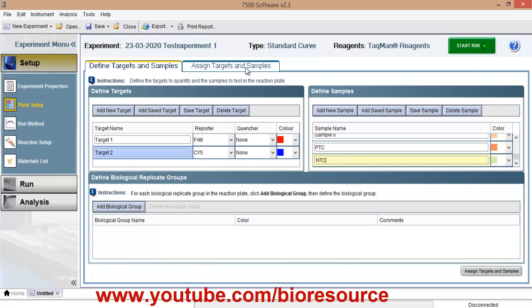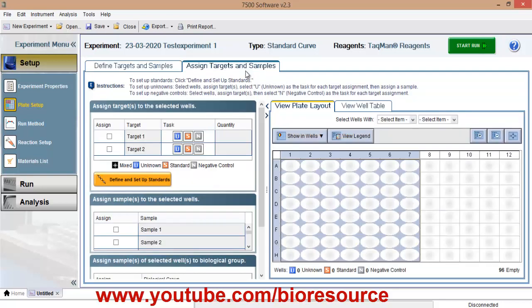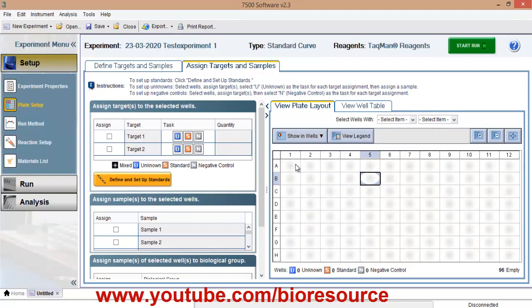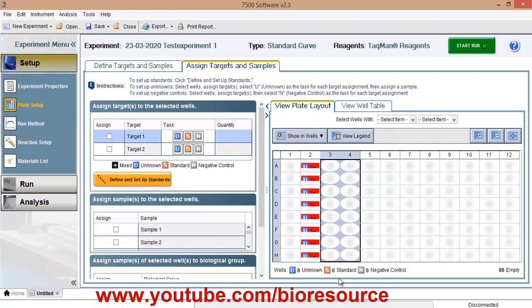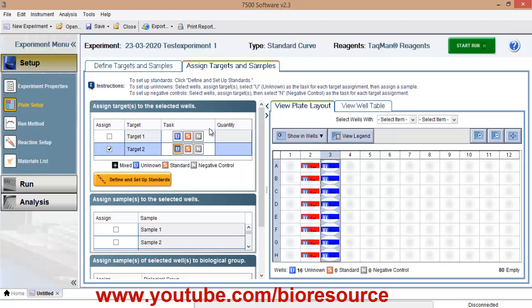Once you go to assign targets, you will get the 96 well format. From there, you can select the wells and assign the targets. So I am setting up target1 and 2 or you can have multiple targets in a single tube. So you can select target1 and 2 also.